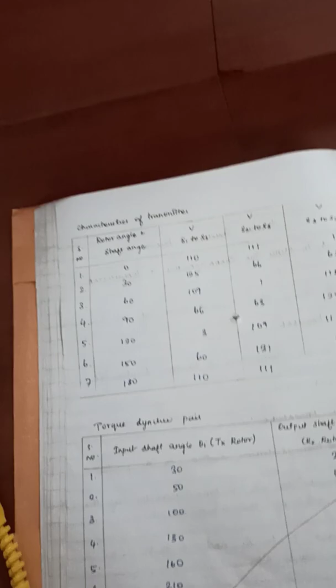If I change the shaft position from 0 degrees to 40 degrees, I can see the voltage changes from 68 to 30. Similarly at 30 degrees, instead of 66, here it is 30. So for every change in rotor position, I measure the voltage value to check whether my transmitter responds to the change in angular position.